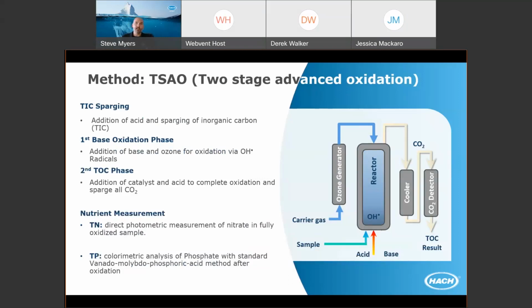So after that starts, we get into the first oxidation phase where a base is added to the sample and the ozone generator is kicked on. This forms hydroxyl radicals in the sample. These are very strong oxidants and oxidize all that organic matter into carbon dioxide, runs it through the detector. Actually, the second phase of this oxidation is when acid and a catalyst are introduced into the reactor to complete that oxidation. That's just making sure that everything is turned into CO2, and then it's run through the detector, and we get the TOC result calculated out of that.